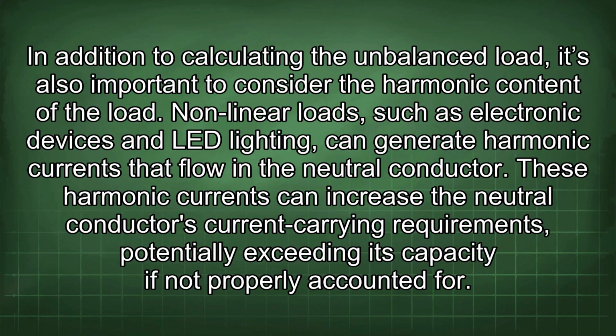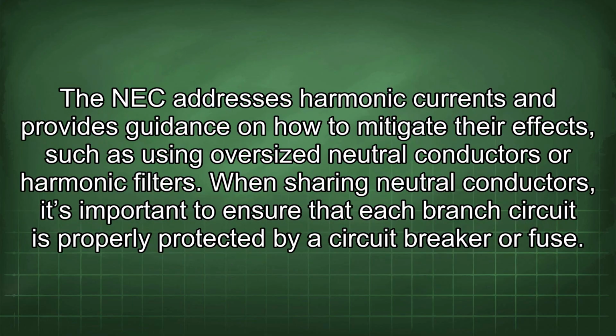In addition to calculating the unbalanced load, it's also important to consider the harmonic content of the load. Nonlinear loads, such as electronic devices and LED lighting, can generate harmonic currents that flow in the neutral conductor. These harmonic currents can increase the neutral conductor's current carrying requirements, potentially exceeding its capacity if not properly accounted for. The NEC addresses harmonic currents and provides guidance on how to mitigate their effects, such as using oversized neutral conductors or harmonic filters.